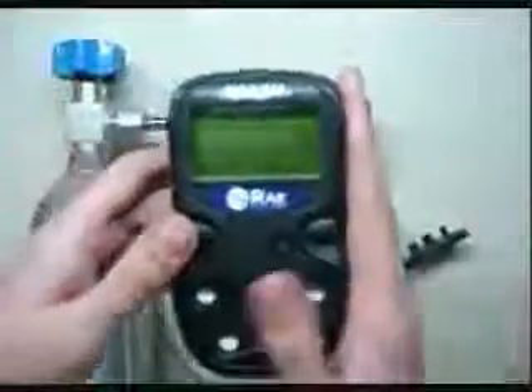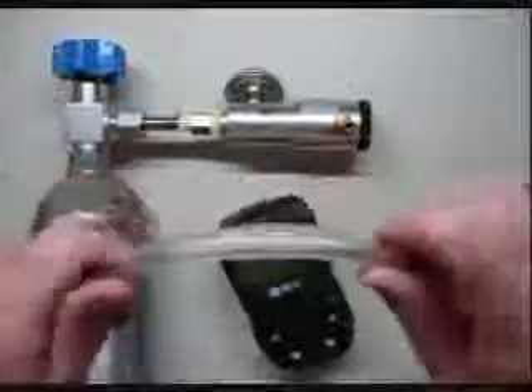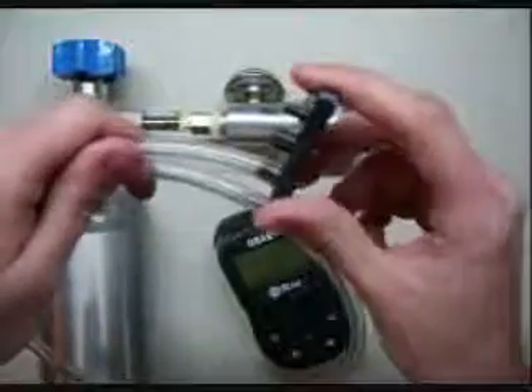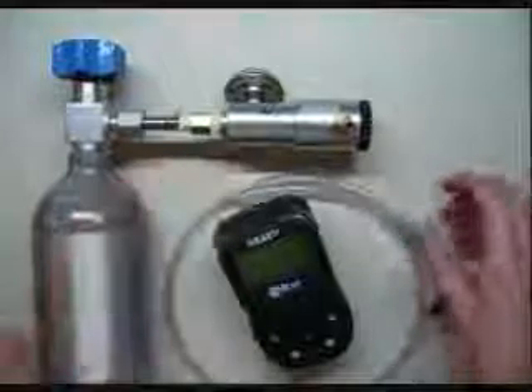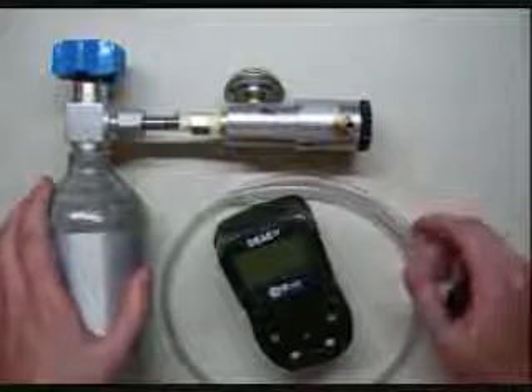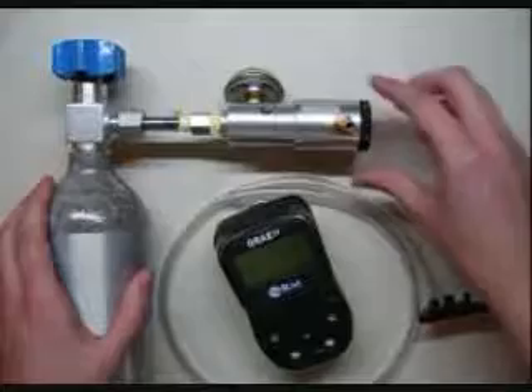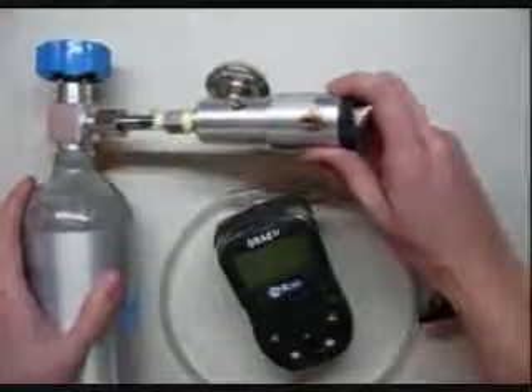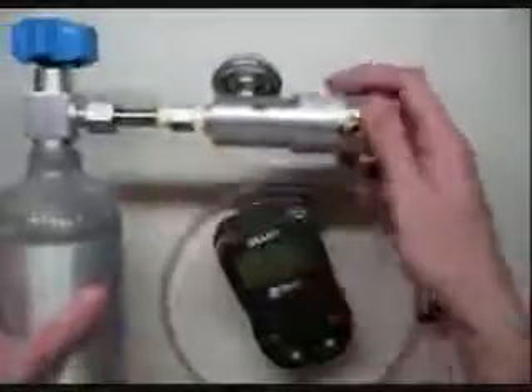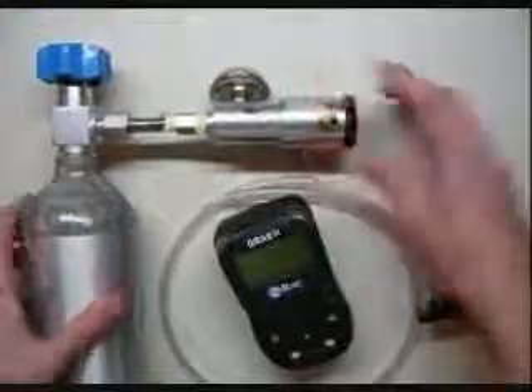What you're going to need is the monitor, a length of tubing, a calibration cup, a cylinder of trusted calibration gas. We of course blend our own here at Ideal Gases. Also a 1.0 liter per minute regulator. This one right here is a multi-flow regulator that will give us whatever flow we need. And that's going to be it.